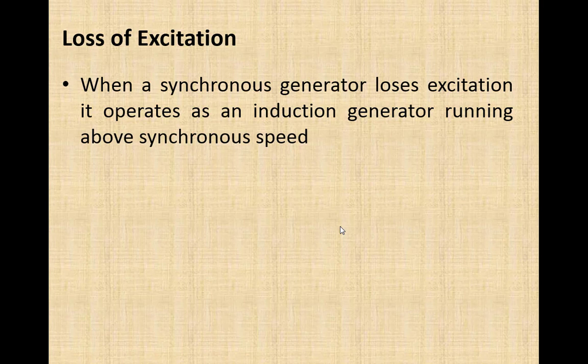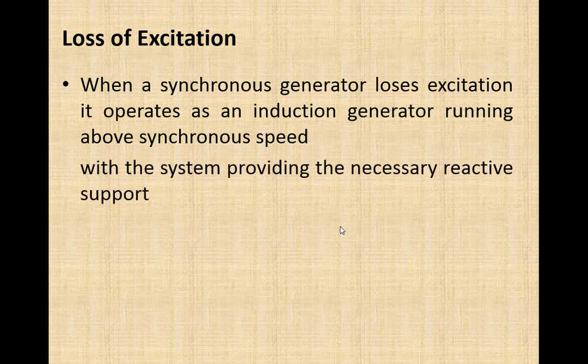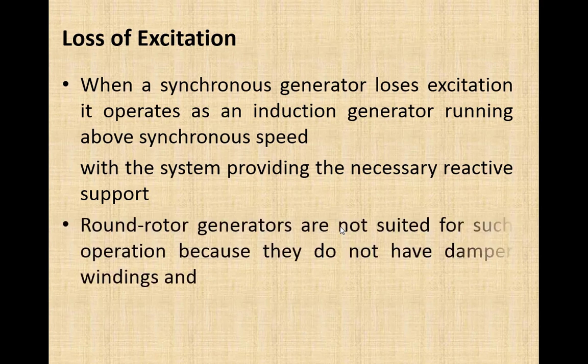When a synchronous generator loses excitation, it operates as an induction generator running above synchronous speed. So its speed will go slightly above the synchronous speed. Only then does a generator behave like an induction generator, with the system providing the necessary reactive power support. The round rotor generators are not suited for such operation of a synchronous generator as an induction generator.